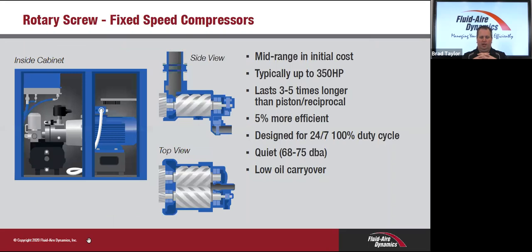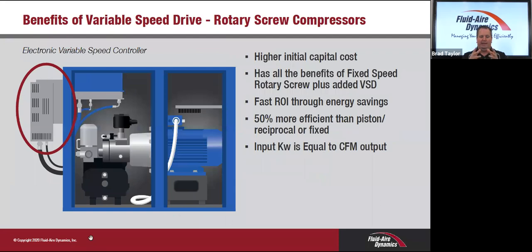Next slide there. The guts of it look similar to this, like a blower on top of a race car. They're more efficient than a piston machine, relatively quiet unless it's super old. It can be a screamer, and in most cases will deliver a lower oil carryover when compared to a piston type compressor. So if we go to the next slide, this will show us, in essence, we're adding a variable speed drive to a fixed speed compressor. Now, of course, it increases the capital cost of the equipment, but there are a lot of other benefits that come with varying the speed of a fixed speed type compressor.